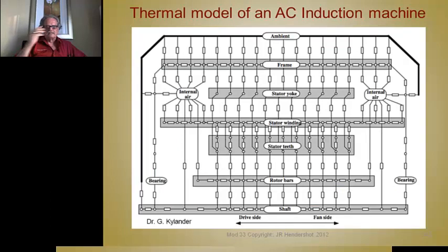This is a thermal model of an AC induction machine that was presented by Dr. Kylander. It's the same idea as Dave Staton's, but you can build a solver for this and calculate this. The problem with these kinds of lumped parameter thermal models is that there are so many variables that you don't know what values to put in the circuit, because the biggest problem is thermal transitions from one surface to another.